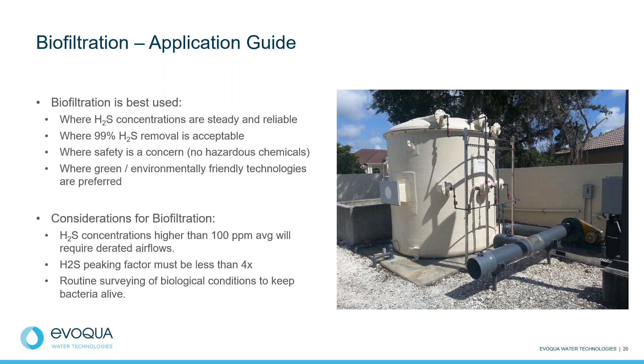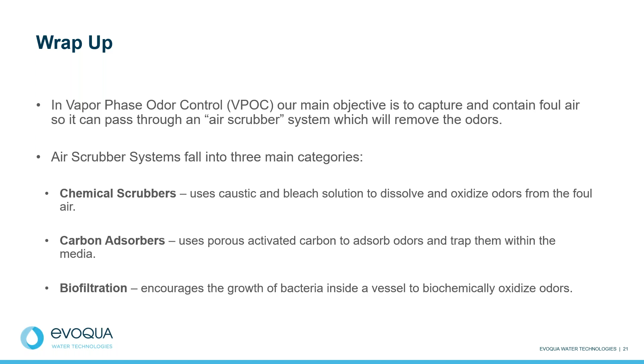So now I know that's a lot of information to cover in such a short period of time, but now to wrap everything up that we learned today. The key takeaway is that for vapor phase odor control applications, our main objective is to capture and contain foul air so it can pass through an air scrubber system and remove those odors. And then of the air scrubber systems, we have those 3 main categories of technologies: the chemical scrubbers, which use the combination of caustic and bleach solution for dissolving and then oxidizing odors from the foul air; the carbon adsorbers, which use the porous activated carbon to absorb and trap odors within the media; and then lastly, biofiltration, which encourages the growth of bacteria inside a vessel that will biochemically oxidize odors.